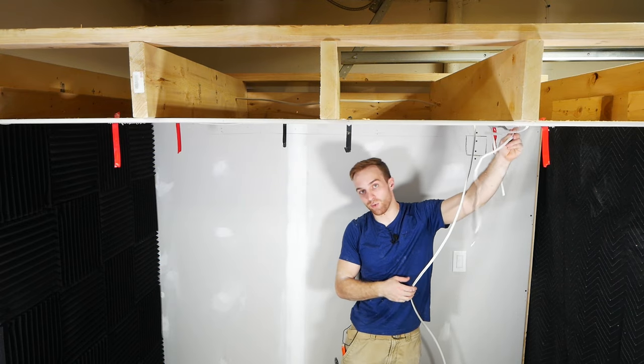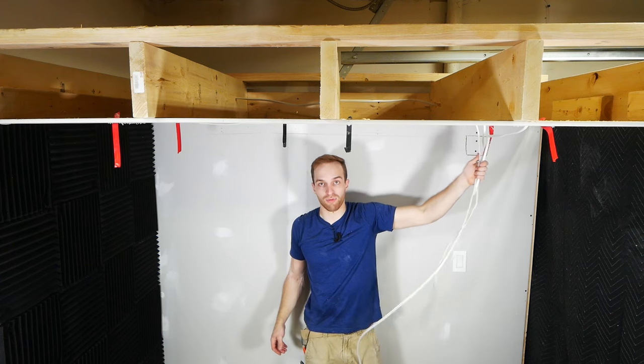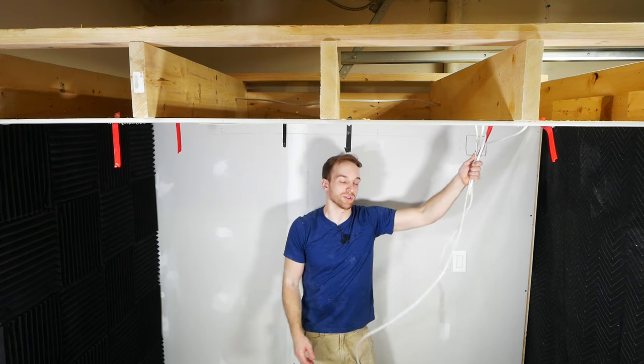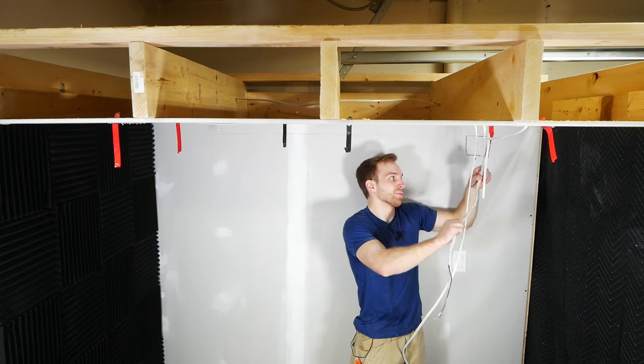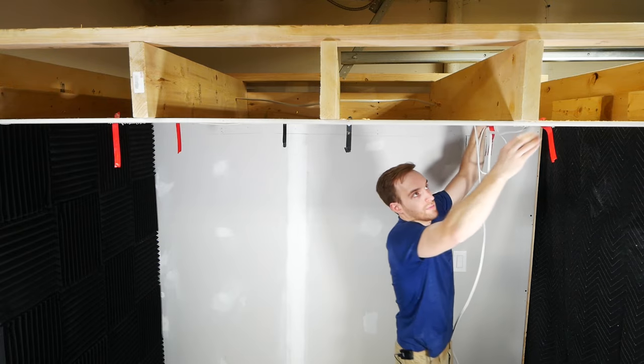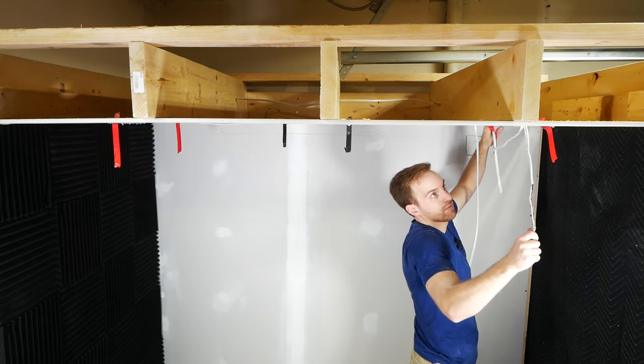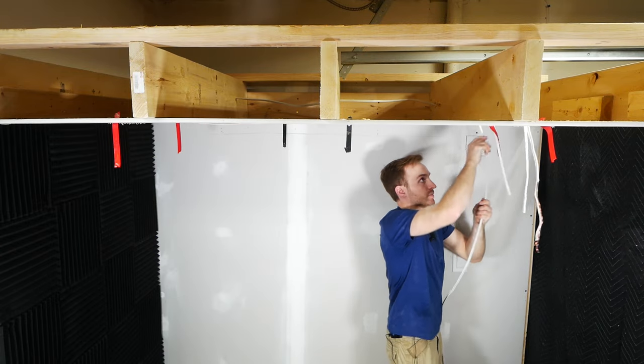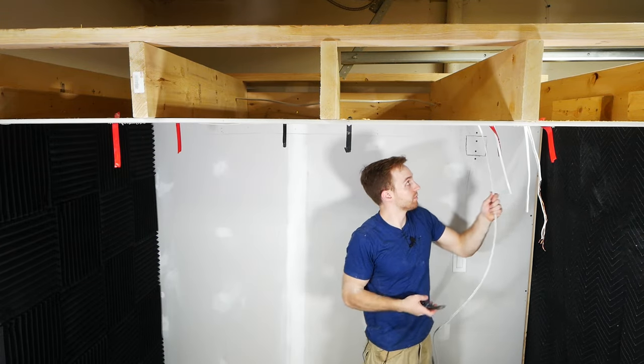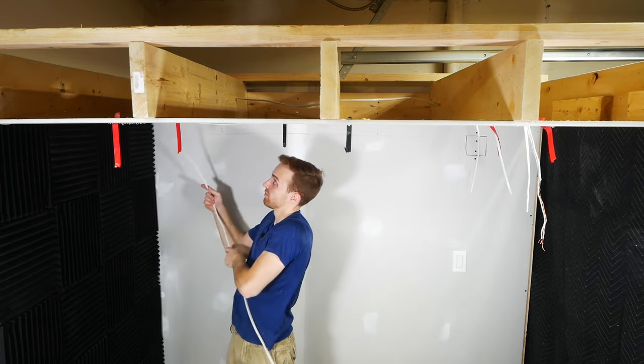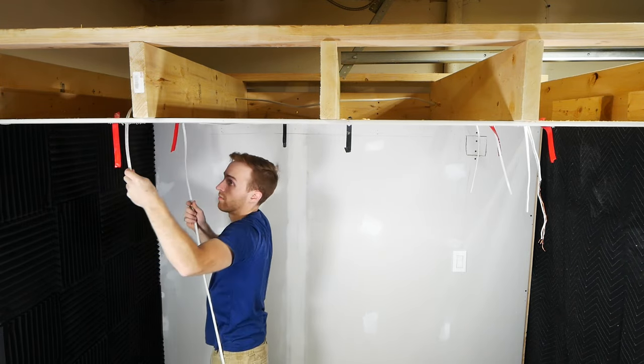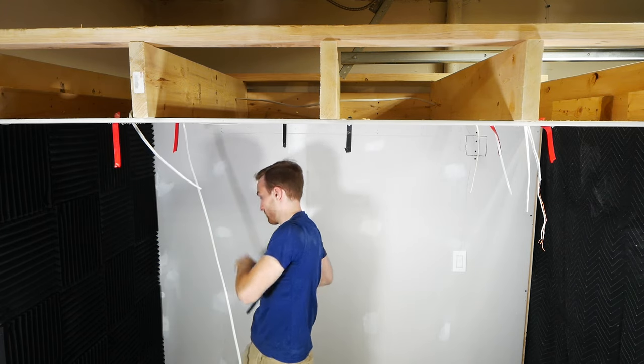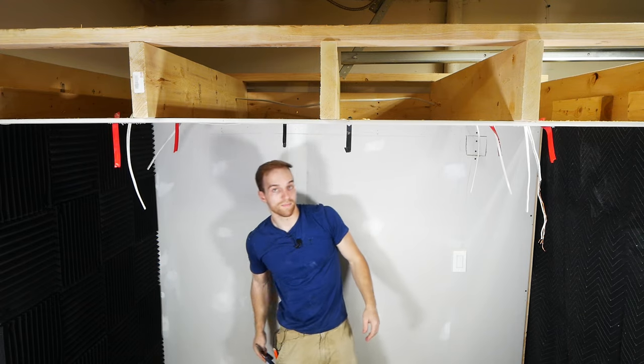Here, I have this wire and it's long enough to reach this hole. I could keep this wire here, however, then I would have three wires in one pot light. That's not ideal. You can do it, but it's just going to be a pain. So if you can avoid it, we want to do that. So I'm going to take this wire, I'm going to run it to this pot light. And then we have two here, we'll have two here. And finally, okay. And this is what you should have. Ideally, you're going to have two wires at each pot light with one pot light with one wire and that'll be your last one.